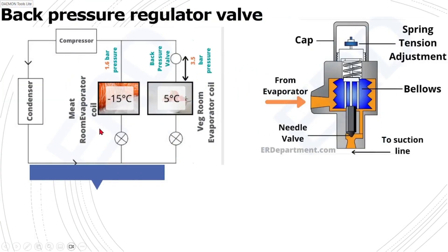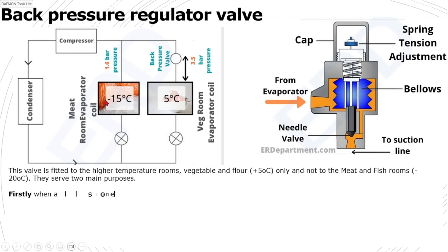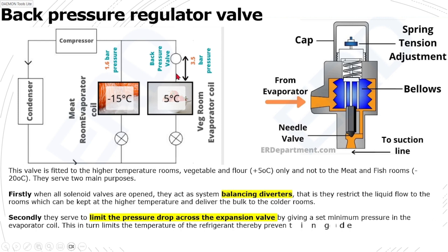Here is how it works in practice. This is the compressor, the condenser, and the expansion valve. In this particular example, you have a meat room to maintain at minus 15 degrees and a vegetable room to maintain at 5 degrees. Normally, the meat room evaporator runs at 1.6 bar. If the back pressure valve is not in place, the vegetable room evaporator would also be subjected to the same 1.6 bar. But with the back pressure valve placed after the evaporator, the pressure at the vegetable room evaporator is held at a higher value — in this example, 3.5 bar.